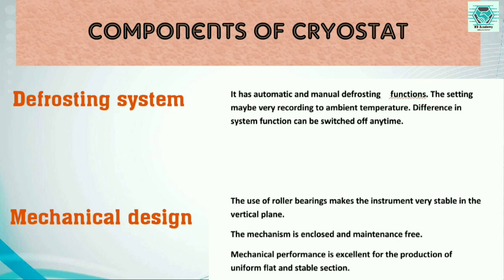In the mechanical design, the use of roller bearings makes the instrument very stable in the vertical plane. The mechanism is enclosed and maintenance-free. Mechanical performance is excellent for the production of uniform, flat, and stable sections.